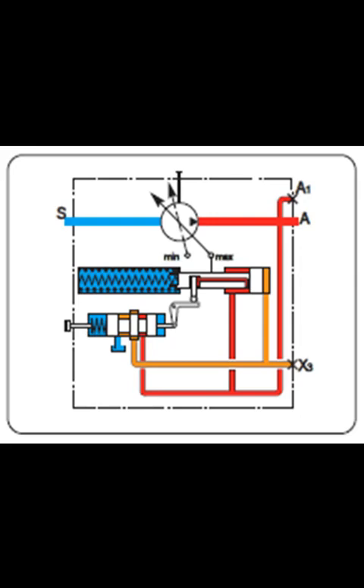LRD Constant Power Control Variation — integral pressure cutoff, fixed setting D. The pressure cutoff is in effect a constant pressure control which swivels the pump back to VG min when the preset working pressure is reached. This function overrides the constant power control, i.e., the constant power control is effective below the preset working pressure. The valve is integrated into the control housing and is set in the factory to a fixed pressure within the range 200 bar to maximum 350 bar.